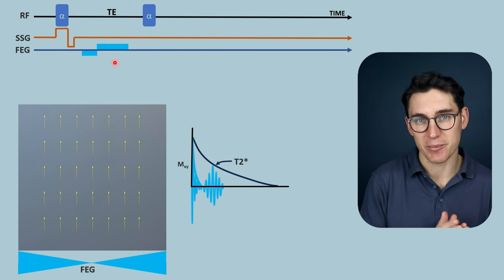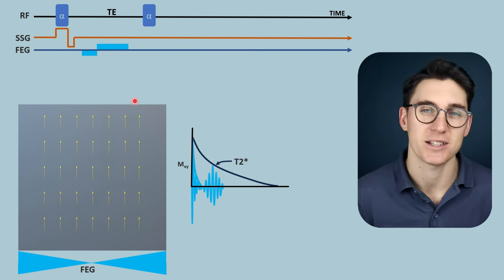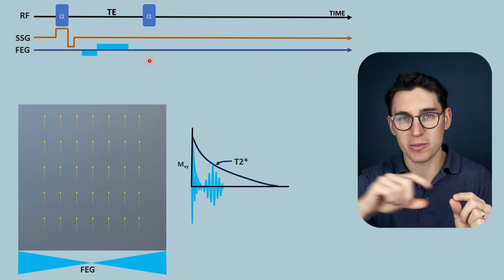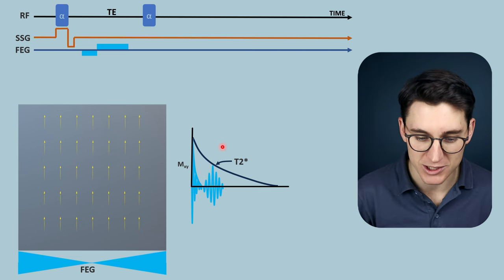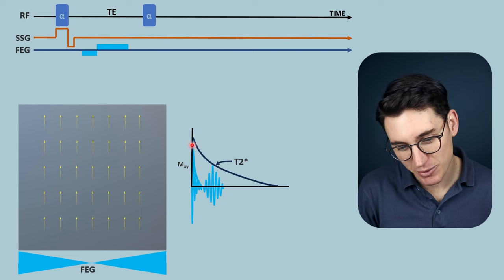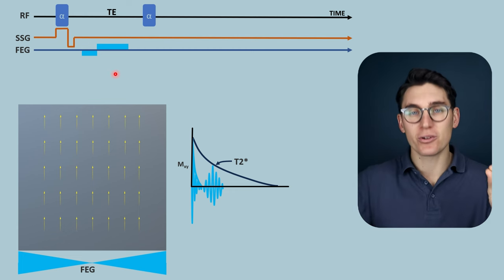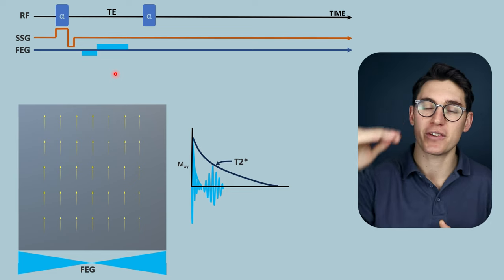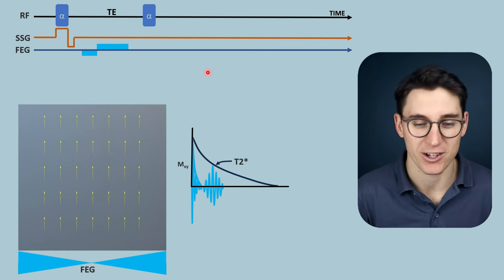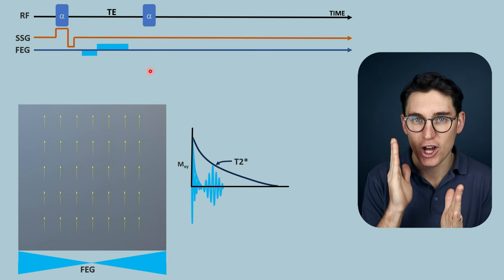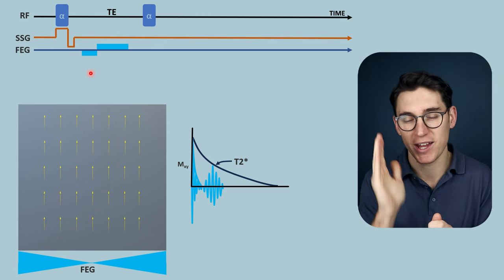In spin echo imaging we could fill up the TR time with multiple echoes or multi-slice imaging, but that isn't as available with gradient echo. Gradient echo images T2 star decay, which happens much quicker than T2 decay. In spin echo we get signal for a long period that we can sample repeatedly, filling k-space between the first and second RF pulses. That can't happen in gradient echo, meaning we need to bring the second RF pulse close to the first — making TR short. Short TR is one of the key features of gradient echo imaging.